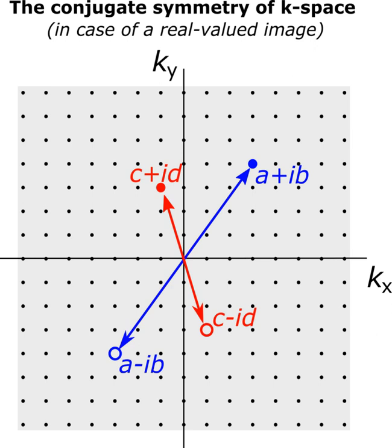Thus K-space information is somewhat redundant then, and an image can be reconstructed using only one half of the K-space, either in the P phase encode direction saving scan time, such a technique is known as half Fourier or half scan, or in the FE frequency encode direction, allowing for lower sampling frequencies and/or shorter echo times, such a technique is known as half echo.